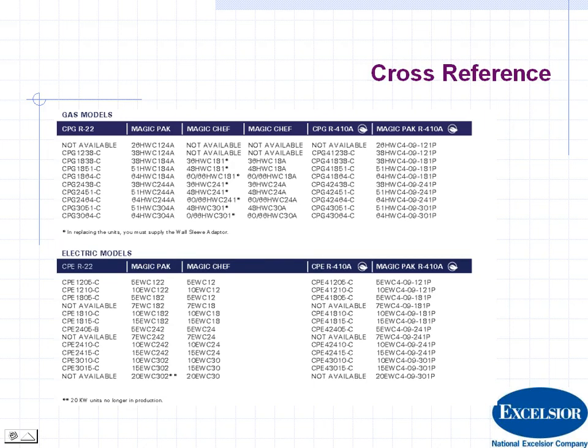Here is a list of replacements, and I do want to make the point that these CPG units are direct replacements for the Magic Pak, the HWCs. This cross-reference chart is on their website, but the physical dimensions, the height, the width, and the depth, the location of the electrical junction box, the gas, electric, the supply and return air are all exact replacements. So if you've got a complex that you have some Magic Packs and you need an alternative, you can talk to one of our Excelsior branches and you can get a quote on it. But there'll be no other modifications that you'll have to make.